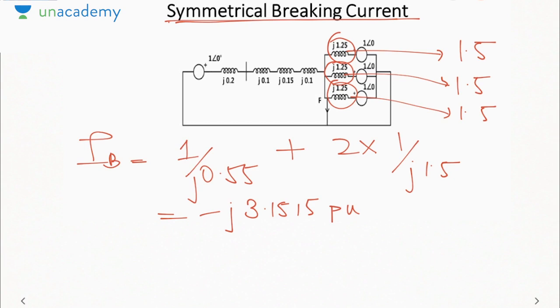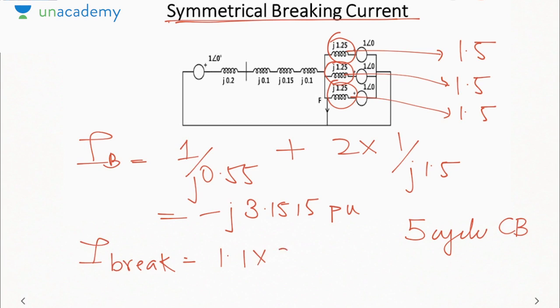Now, to find the breaking current, we have to take the speed of the circuit breaker into account. So let me assume a 5 cycle circuit breaker. So I breaking will be 1.1 into 3.1515 pu. And the actual value will be multiplied by the base current, which is 2187.